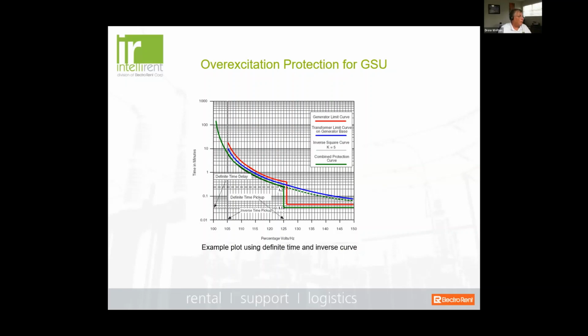So how do we set a volts per hertz limit? Well, it's based on time and then percentage of volts per hertz. So all your transformers come with a volts per hertz withstand capability, and these are thermal limits. And these thermal limits should be defined in the transformer spec. If not, there's plenty of resource material out there to find in terms of what that setting should be. But you'll notice here that you have an overexcitation plot for the generator itself, its limitations, and then the transformer limitations, and then the setting that is a bit more conservative than both, which means that if I have, let's say, volts per hertz of 120%, and that's around for less than a minute, I'm probably going to trip and take the transformer offline.